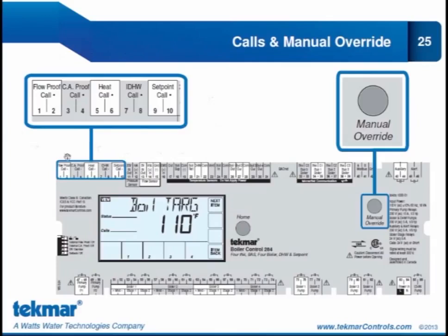You can see this is where we wire our calls, and there are 5 different calls that can be connected. Our flow-proof call, and that would be if we are using something to prove flow for the primary pump sequencing. If we are using a flow sensor, then we simply connect a jumper across these 2 terminals. However, if we're using any other flow sensing device, we would connect that to the flow-proof call terminals. Our next set of proof call is the CA proof call. So we can connect the end switch from the motor, from the CA damper, into the CA proof call.